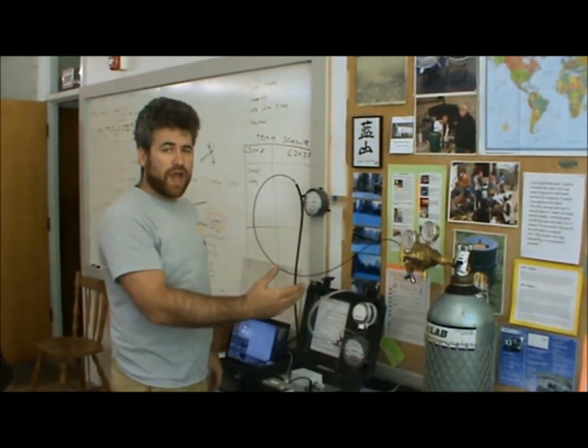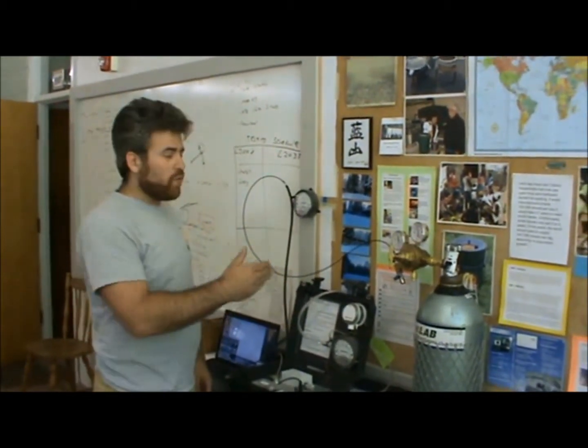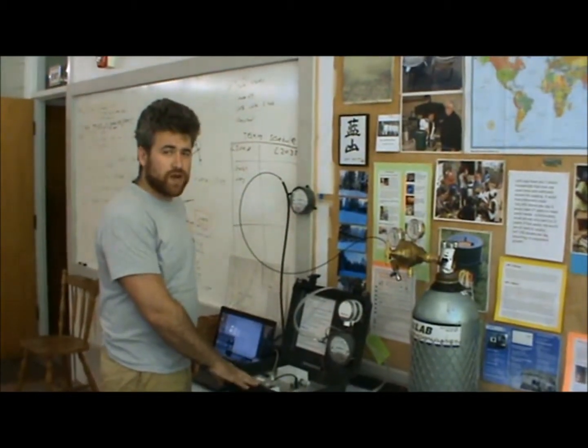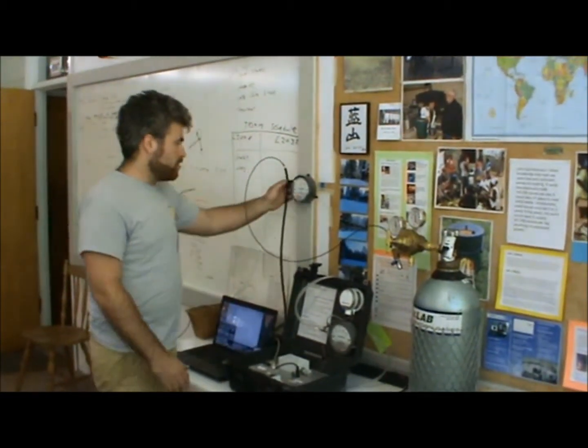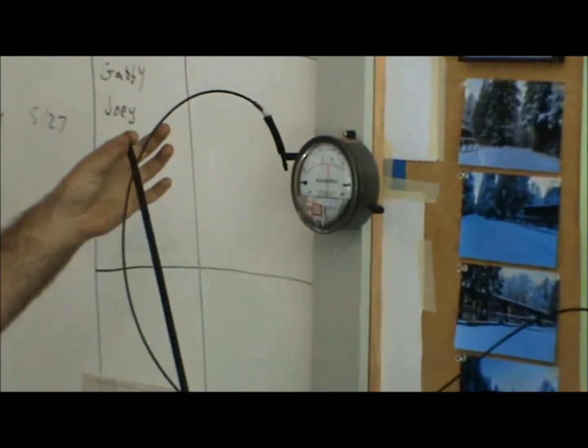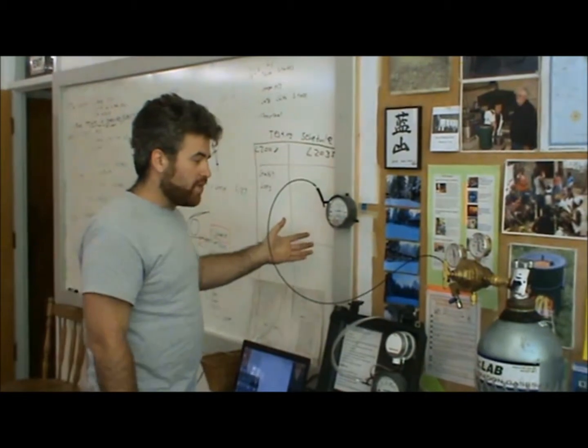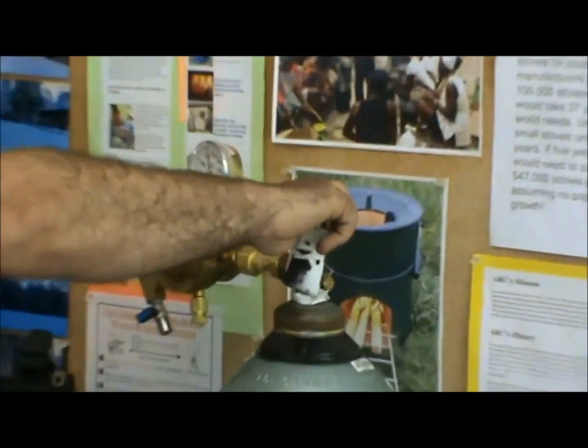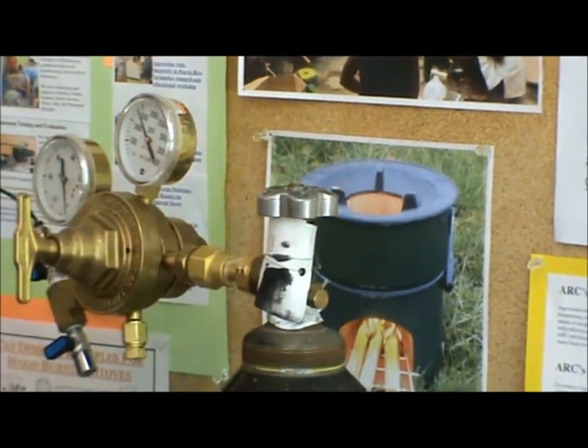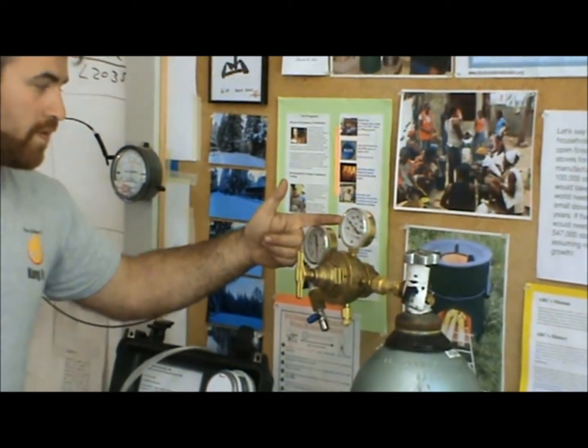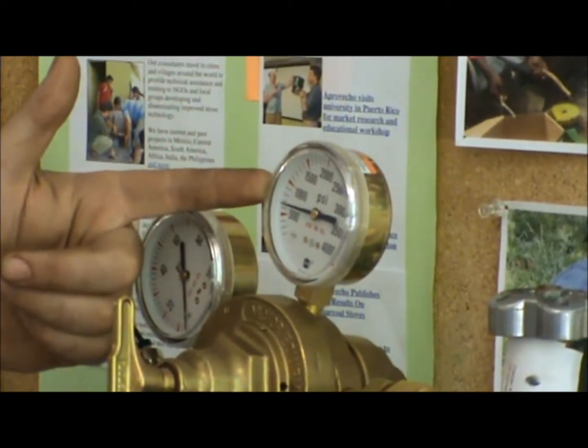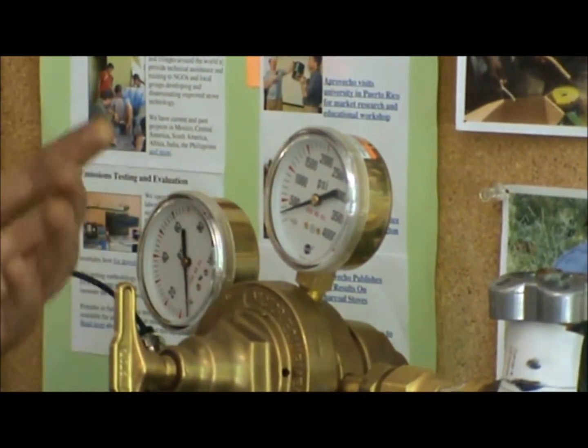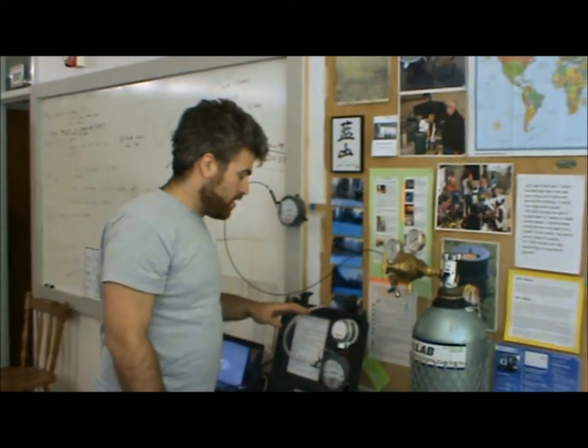So after communicating with my CO2 sensor while the gas is still running, I can disconnect my gas and turn it off. I want to do this in a specific order so I don't make the sensor box work too hard. The very first thing I'm going to do is disconnect my sensor box from the magnehelic gauge. I've got gas coming out now, and all I have to do to turn off the gas is turn this big knob at the top. Turn it down, and I can see the pressure inside my regulator dropping. And when it goes to 0, I know that I have no more flow going out of my system. So now we're waiting that 10 minutes for the sensor box to sample clean air, after which we can process the data.